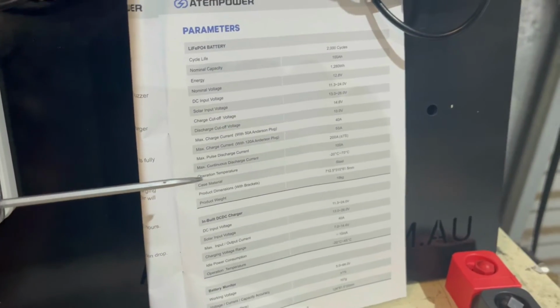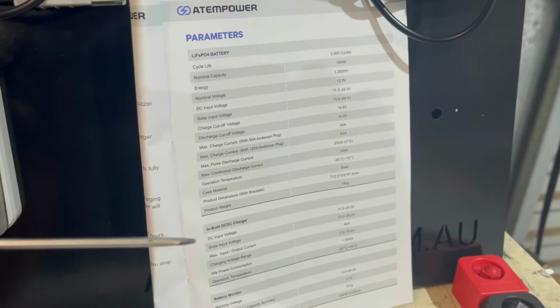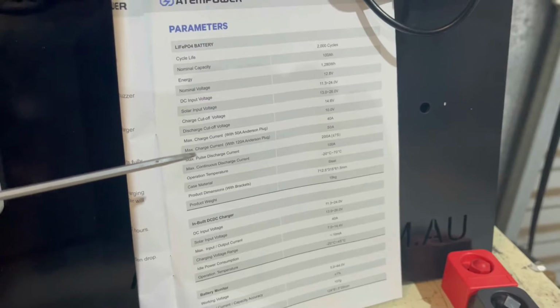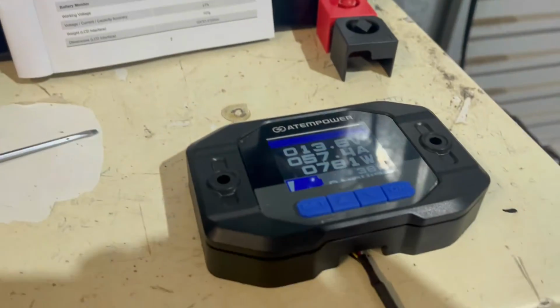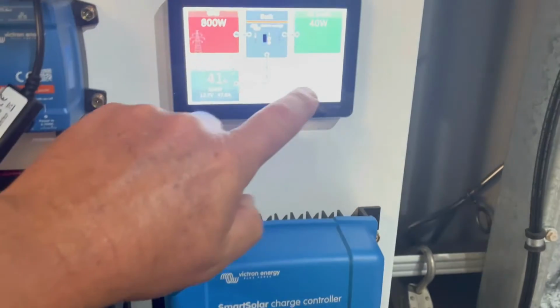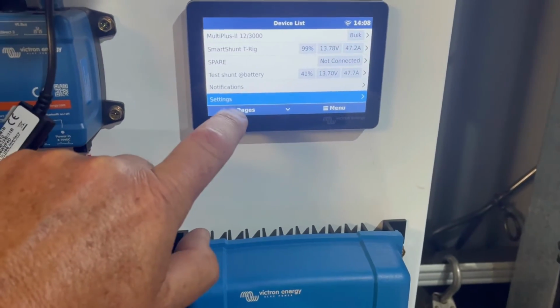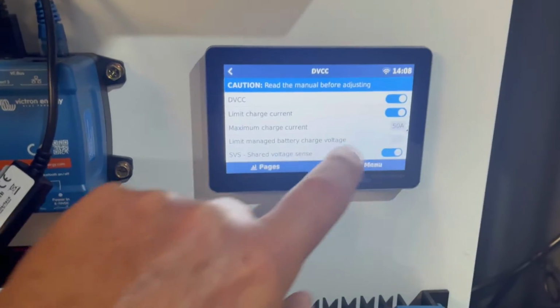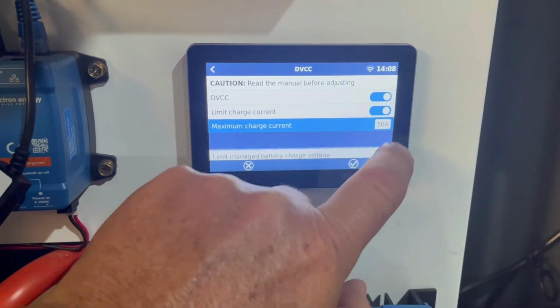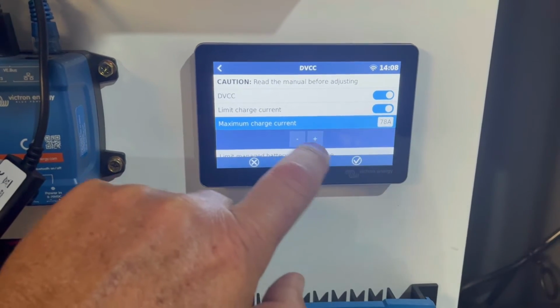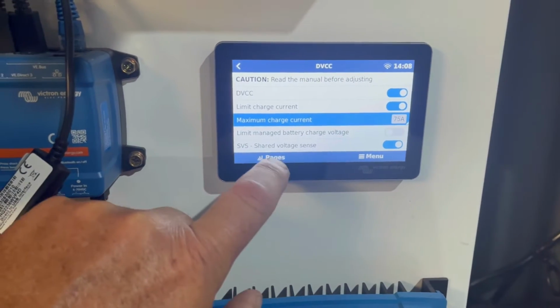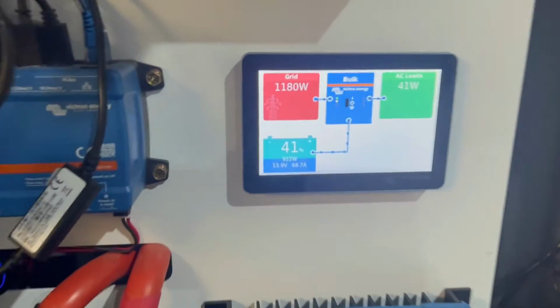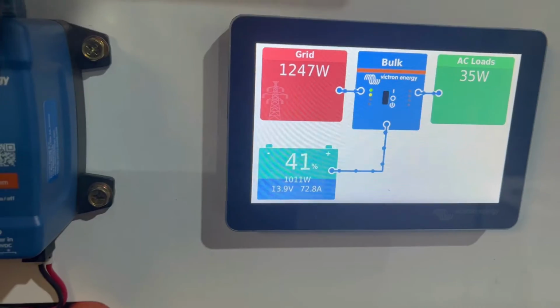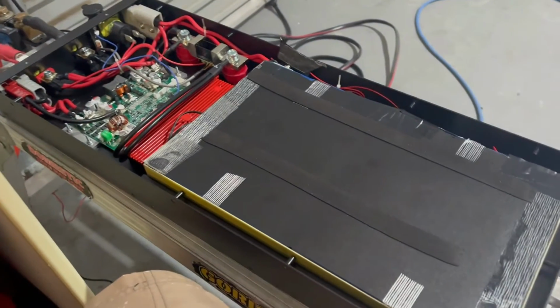So what I might do is wind up the charge current and see whether the BMS trips, and then we'll know. So if we just go into DVCC and wind it up to say 75 amps - click OK. Okay, so now as you can see the charge current has come up. If the BMS trips and the FETs open, then we'll know it can't take more than somewhere between 50 and 75 amps.